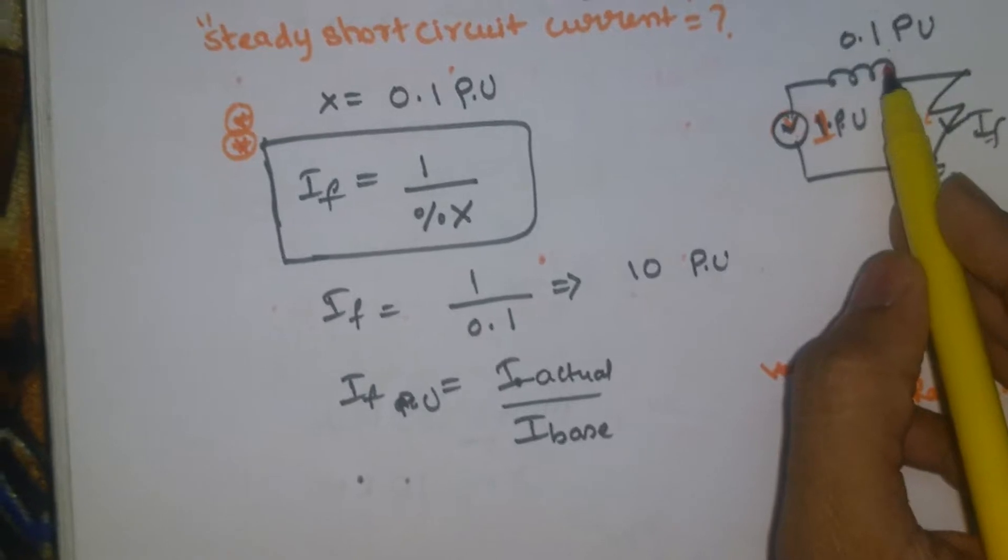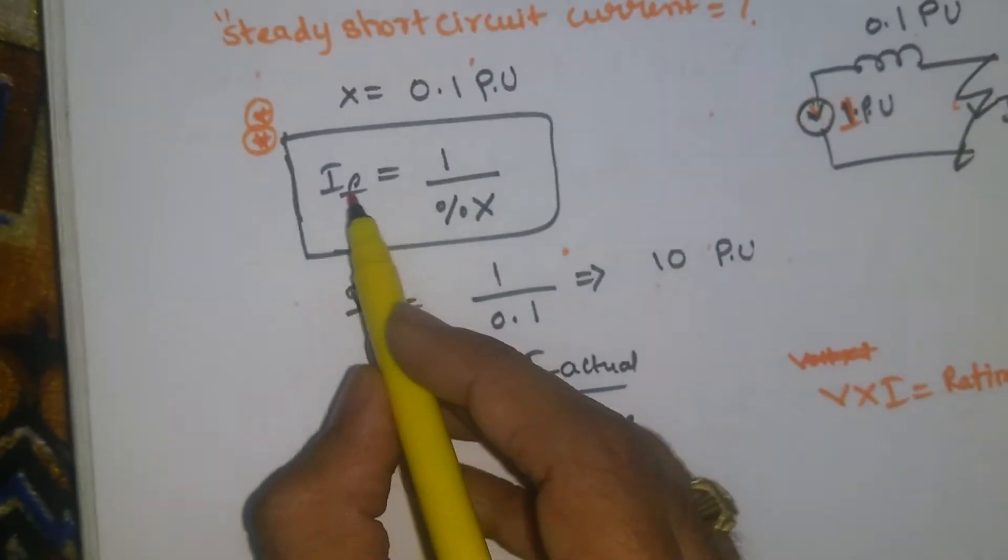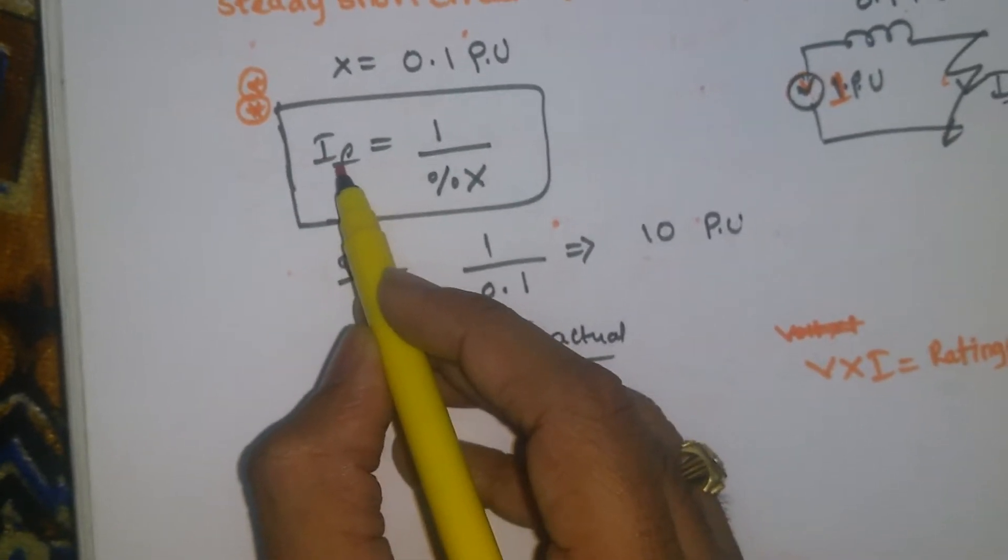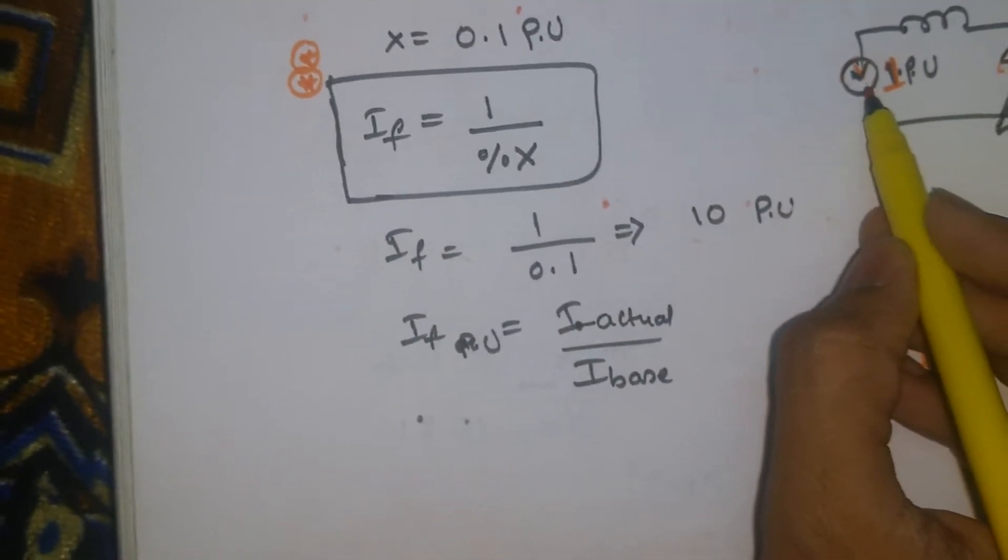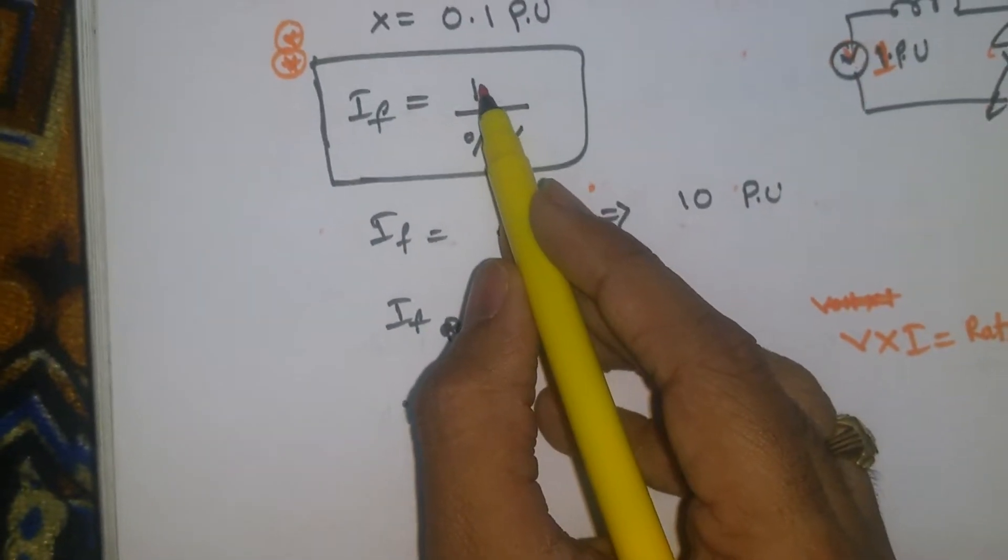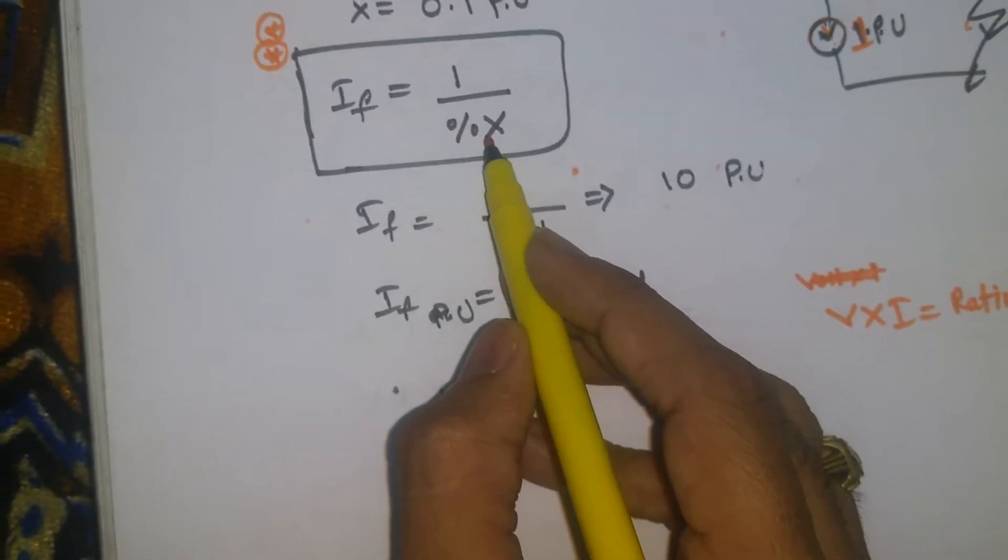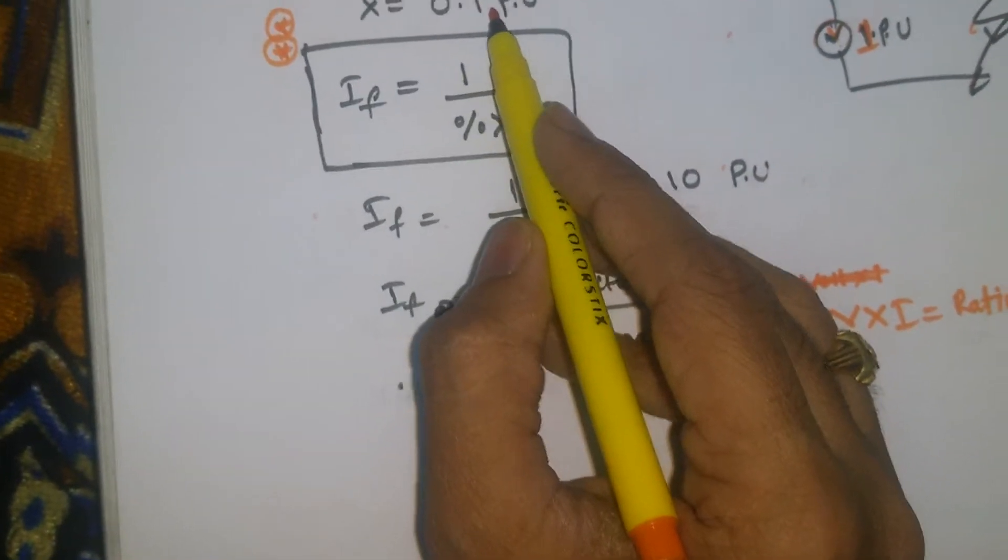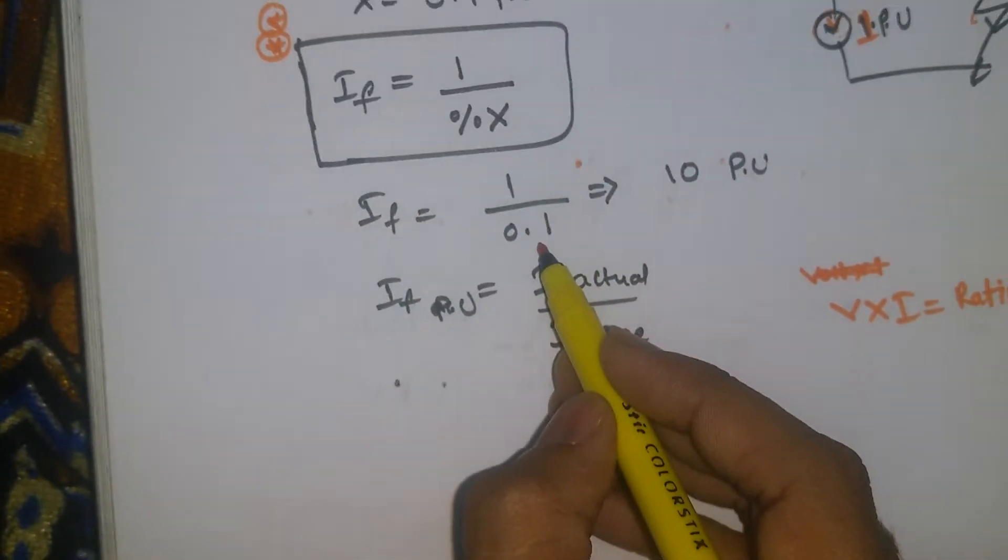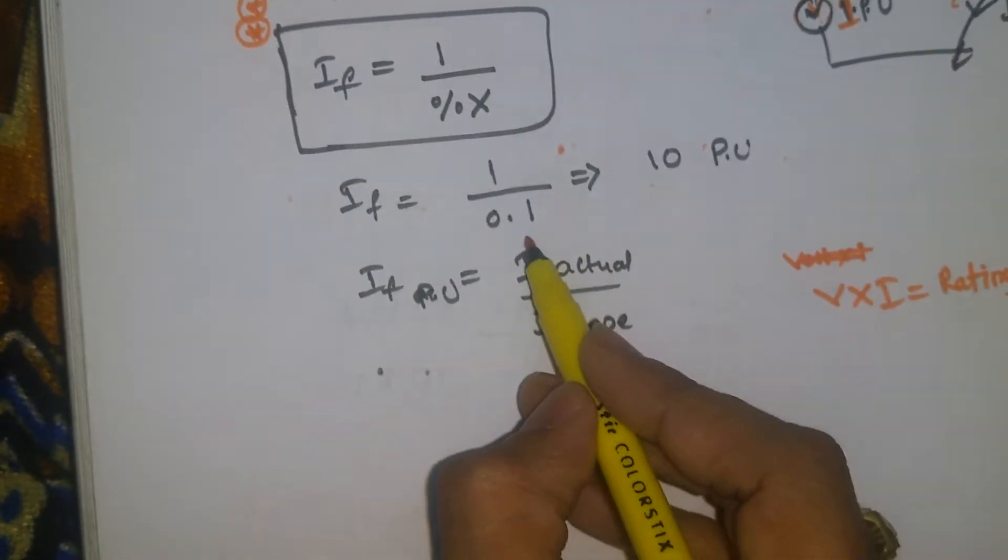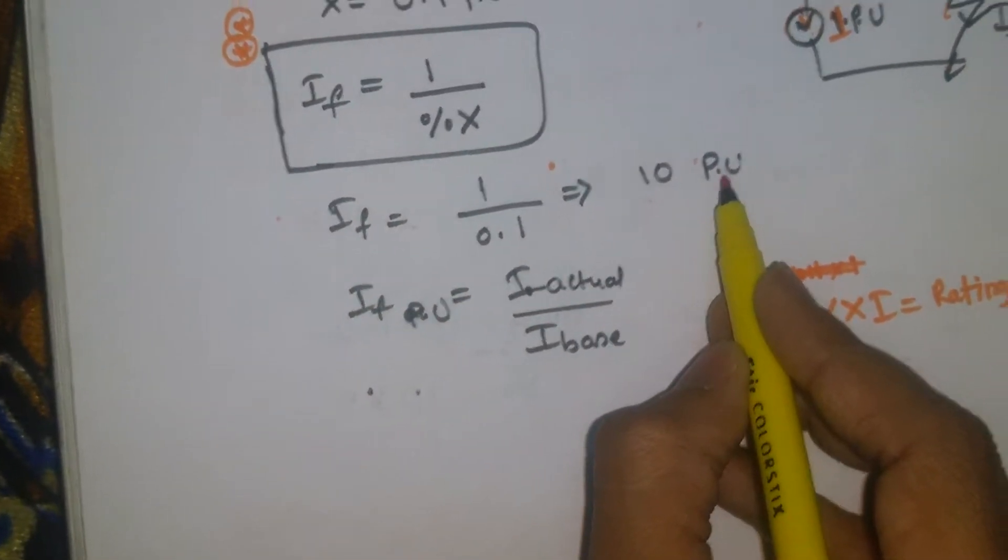Simple, we have a voltage source, we have an impedance, we need to find the current. V is equal to IR, so V by R is equal to I. Like that only, fault current we need to find. So the voltage is 1 per unit, so If is equal to 1 by percentage X. In the place of R, I am giving percentage impedance value. So I have value in per unit system, that is 10.